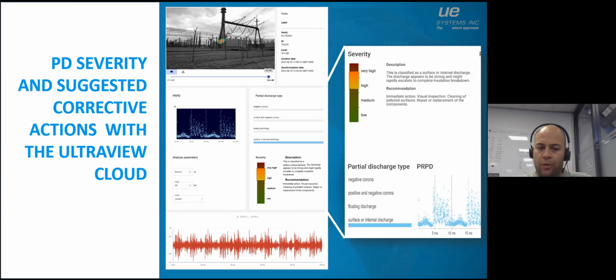If you fill in the distance, the voltage level, and the type of asset you're inspecting, it will automatically determine the severity and give you a first advice on what to do. Also the partial discharge type—on the snapshot you see a blue line and the other 3 are grayed out. That means the sound it's picking up here is surface or internal discharge.